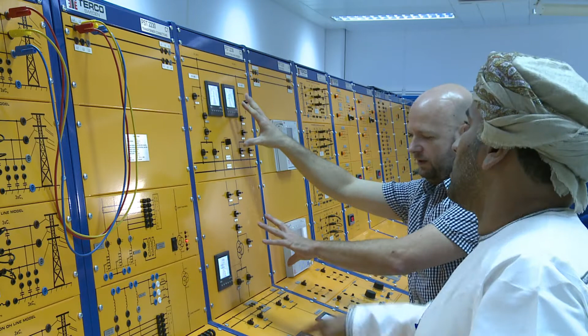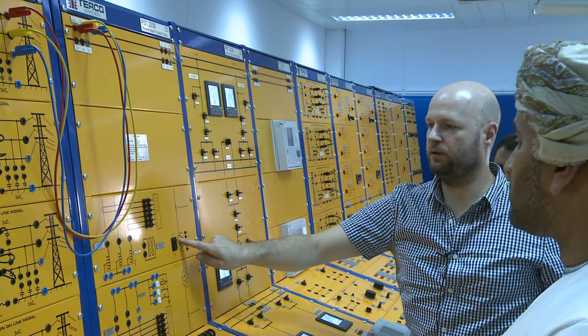Here we have a star-star transformer with a delta winding as well. He's already taking the input from here, so we have this one, and we can connect through all of this. Once again, we have connections, and this control one is already internally connected. But we need to make the connections inside the transformer, so on the HV side we need to make a Y connection here.